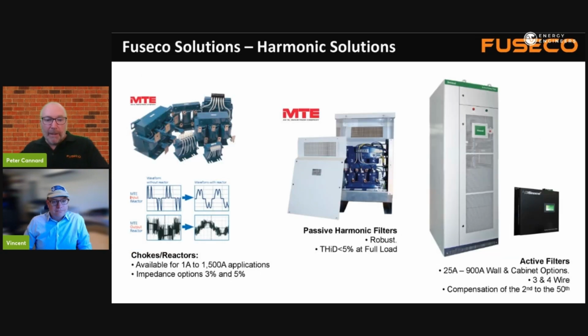There are lots of products out in the market that deal with power factor and harmonic solutions. We've got a number here on the left-hand side, basic chokes and reactors that we can use on the input of variable speed drives, but also on the output. So we can clean up the input, turning a horribly distorted current waveform into a much cleaner one - still a little lumpy and bumpy, but far better. On the output of variable speed drives, you can clean up this high frequency switching into a much cleaner sinusoid, or close to one.